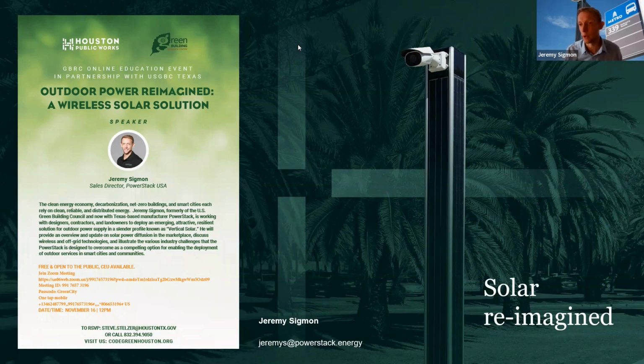The foundation becomes the question of what it will attach to. We have talked to some that have a big concrete block that they end up moving around for some of their systems, and that could have 4 bolts on it to receive a PowerStack. That could be one option: a sturdy footing that lays on top of the soil. Another solution would be to move it from existing concrete pad to existing concrete pad, and you drill 4 holes and use Dynabolts in there. They set overnight, and now it's ready to go.